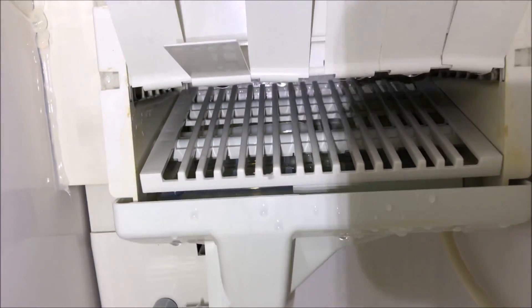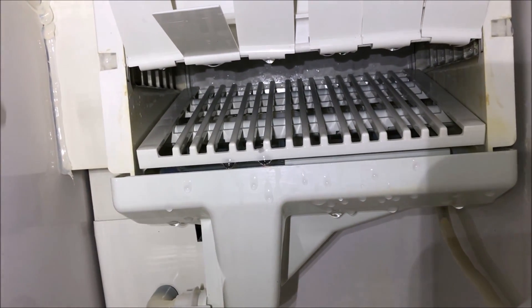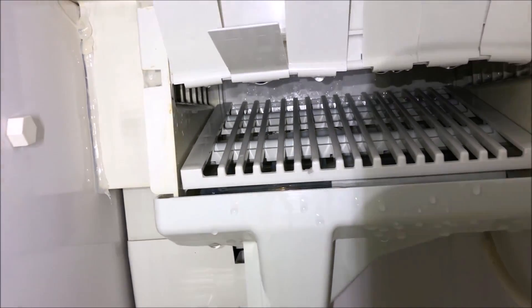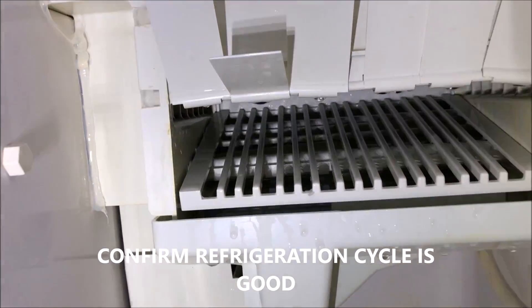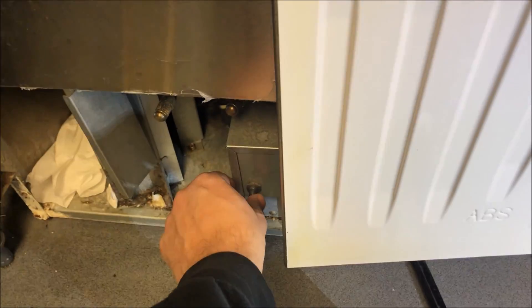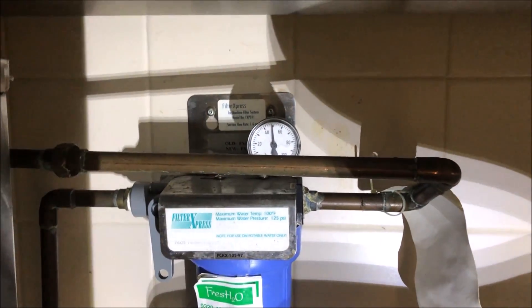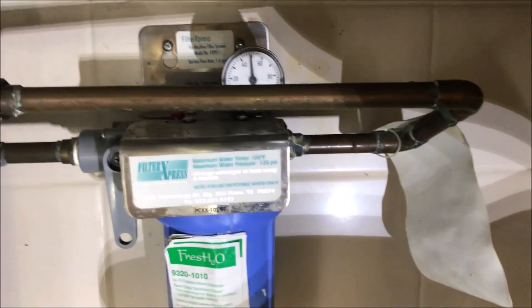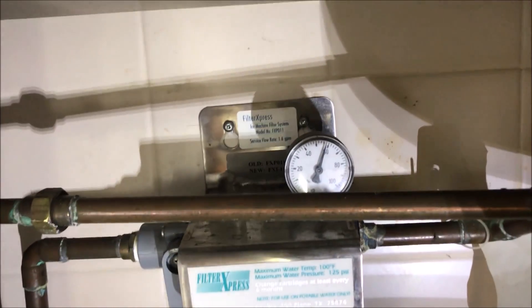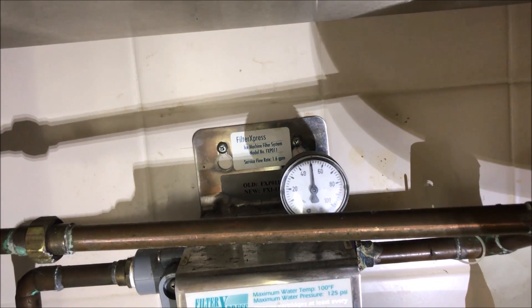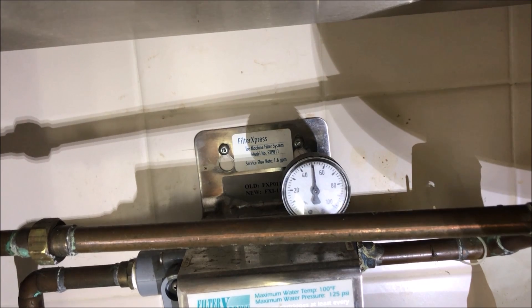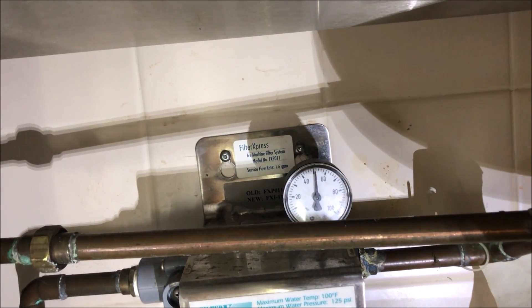So I did just complete a cycle. That tells me the refrigeration cycle is good. I don't need to worry about the refrigeration cycle now. Next thing we're going to do is fire up and let's see what our water pressure is. We have really good water pressure here. You can see that solenoid was open. So water pressure is not going to be an issue here.